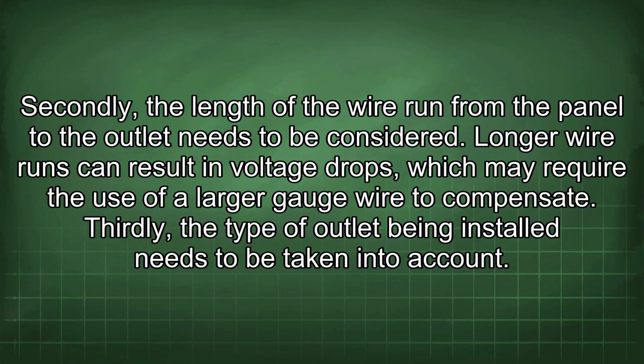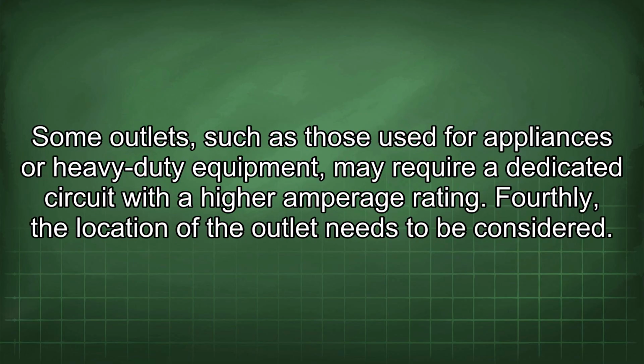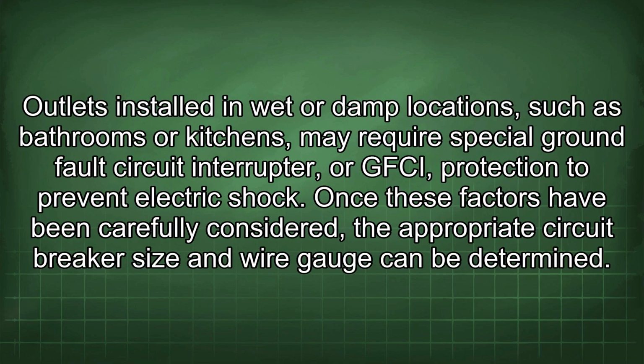Thirdly, the type of outlet being installed needs to be taken into account. Some outlets, such as those used for appliances or heavy-duty equipment, may require a dedicated circuit with a higher amperage rating. Fourthly, the location of the outlet needs to be considered. Outlets installed in wet or damp locations, such as bathrooms or kitchens, may require special ground fault circuit interrupter, or GFCI, protection to prevent electric shock. Once these factors have been carefully considered, the appropriate circuit breaker size and wire gauge can be determined.